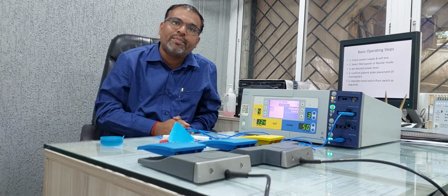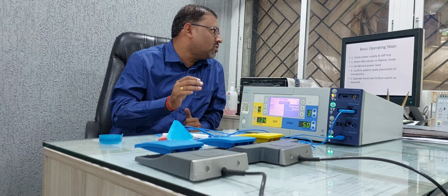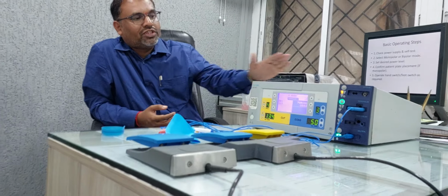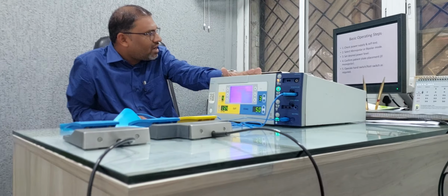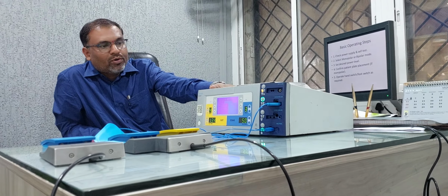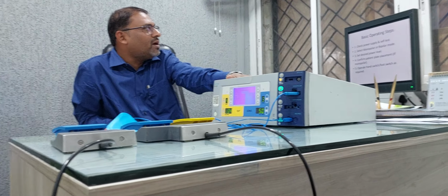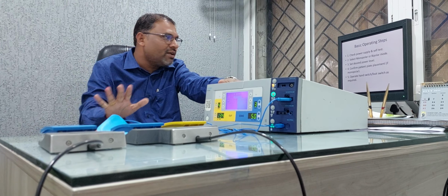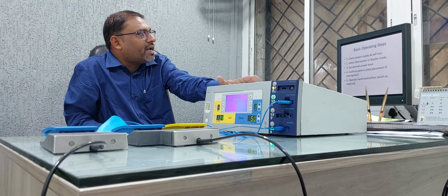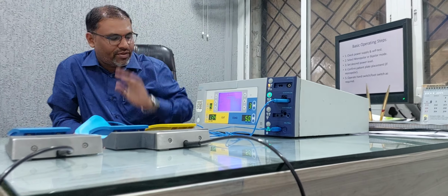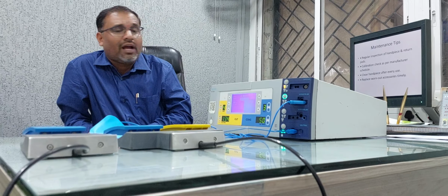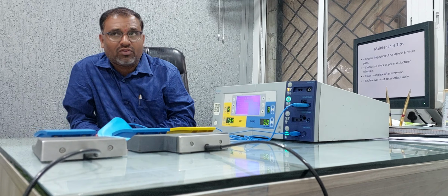So again I am going to repeat the basic operating modes for the machines. First of all, check the power supply, check the self-test, right? Select monopolar or bipolar mode. Always remember to confirm the patient plate is connected properly for the monopolar. Operate the hand switch or foot switch if required. Right? And what are the maintenance tips for cautery machines?